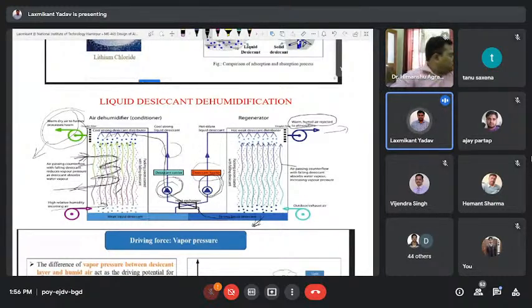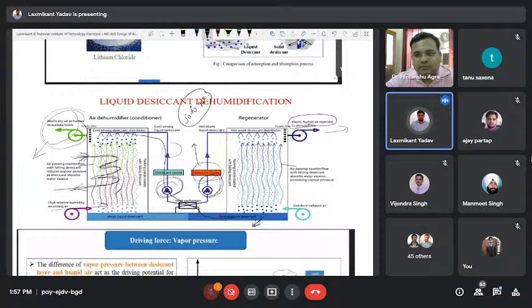However, in the case of solid desiccant, which we will discuss further, it is a simple wheel, so there is no requirement for an adsorption chamber, regeneration chamber or ducts to flow the liquid. Only one wheel is rotated and continuous adsorption and desorption takes place. So there are advantages and disadvantages. Here the regeneration temperature requirement is low, even 50 to 70 degrees Celsius. However, in the case of solid desiccant, we will discuss that the regeneration temperature for some desiccants like calcium chloride is higher, around 100 to 120 degrees Celsius, or even higher.